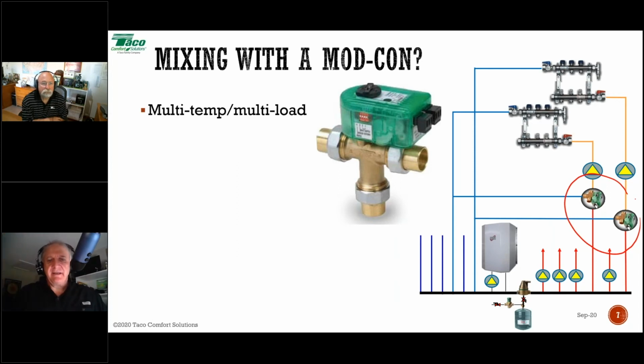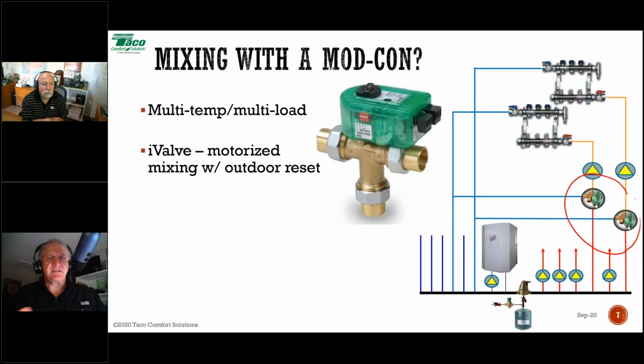Then you can add, in a multi-temp, multi-load system, something like this, which is a Taco iValve. It's a motorized mixing valve, and in that green head, there's an outdoor reset control built in. So you put a separate sensor, one sensor out for each one of these heads. All right, so if you get two heads, you'll have three outdoor sensors. You have the boiler outdoor sensor and the two radiant outdoor sensors. All right, but what you'll get is that'll reset the water temperature for my high temperature radiant, and the separate valve will reset the water temperature for my in the slab radiant.